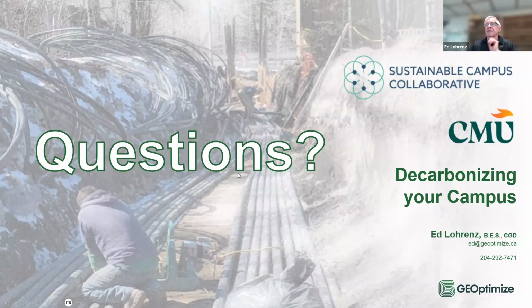Yeah, we did a study in conjunction with Efficiency Manitoba, and we're working on it right now - what's often called energy foundations. There are helical piles screwed into the ground, and pipe can be installed in those. We've got a couple of houses where we've done that, and it's enough to heat and cool those houses, which are about 2,800 square feet. They've got enough piles under them to do the heating and cooling, though it varies a bit.